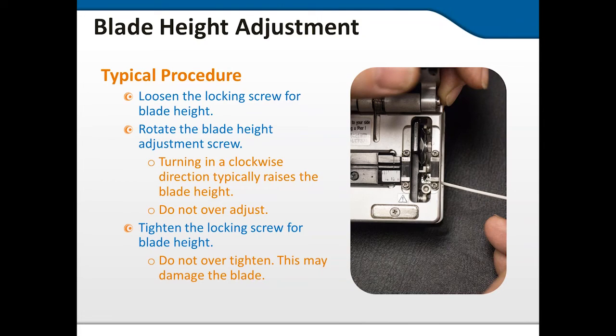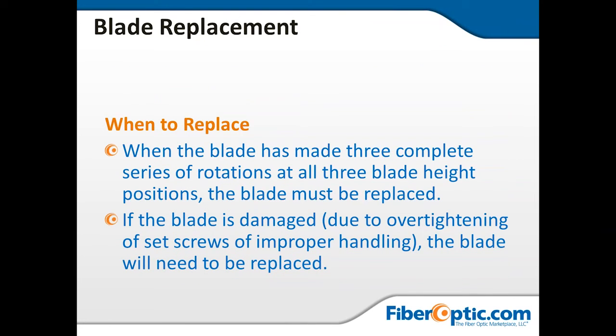Blade replacement. When to replace? When the blade has made 3 complete series of rotations at all three blade height positions, the blade must be replaced. If the blade is damaged due to over tightening of the set screw or improper handling, the blade will need to be replaced. That's why it's very important for technicians to document as much as you can the number of times you've cleaved with the cleaver.